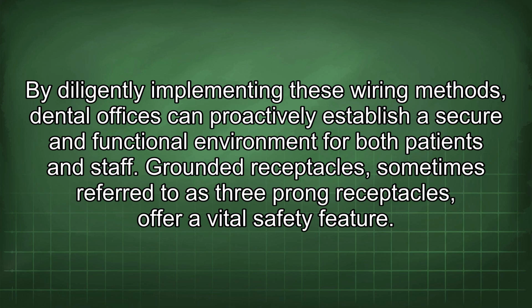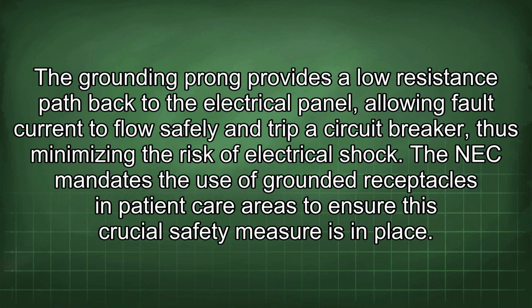Grounded receptacles, sometimes referred to as three-prong receptacles, offer a vital safety feature. The grounding prong provides a low-resistance path back to the electrical panel, allowing fault current to flow safely and trip a circuit breaker, thus minimizing the risk of electrical shock. The NEC mandates the use of grounded receptacles in patient care areas to ensure this crucial safety measure is in place.